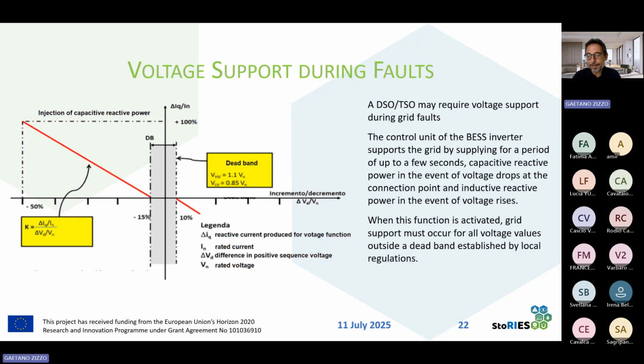Reducing the voltage of the node and bringing the value among the normal operating ranges, all the generators close to that node can stay connected without triggering of their interface protection relay. So: stay connected during the fault and help the grid during the fault. Two functions that batteries can provide easily because they have a very quick response to a control signal coming from the grid, or to a control signal activated by the measuring systems on board of the battery storage systems that can measure locally frequency and, in this case, voltages.